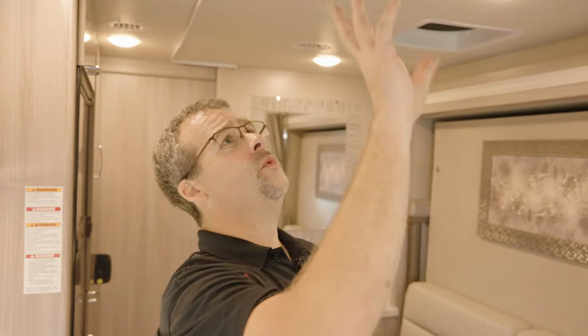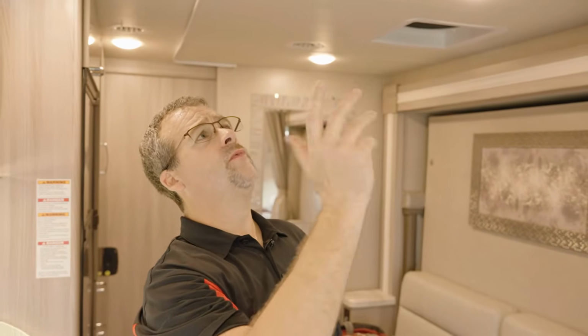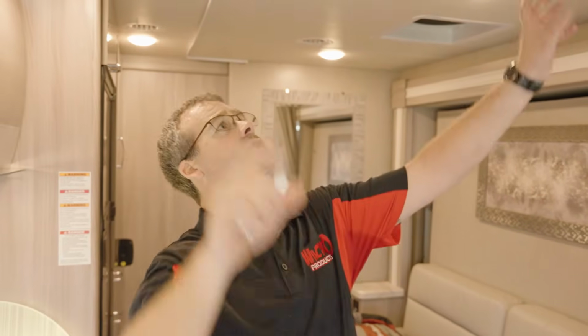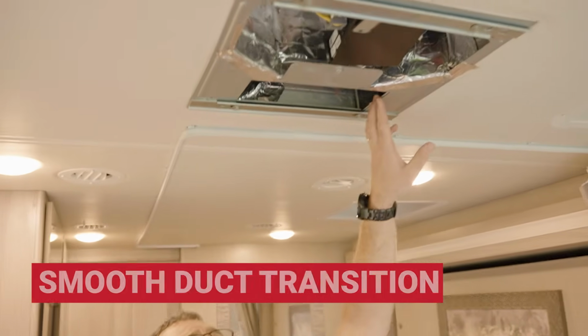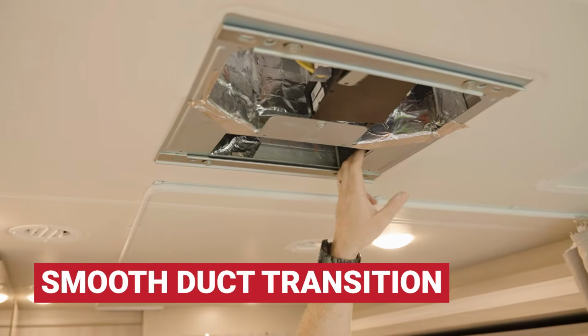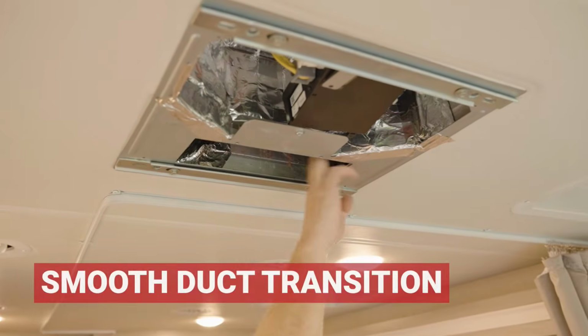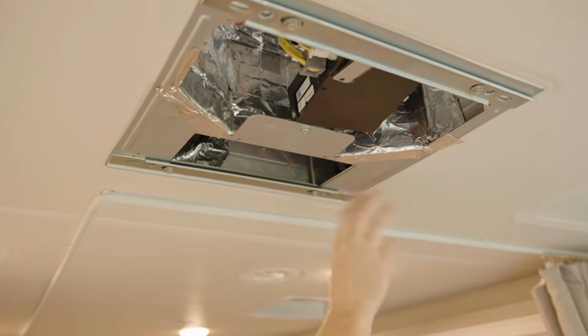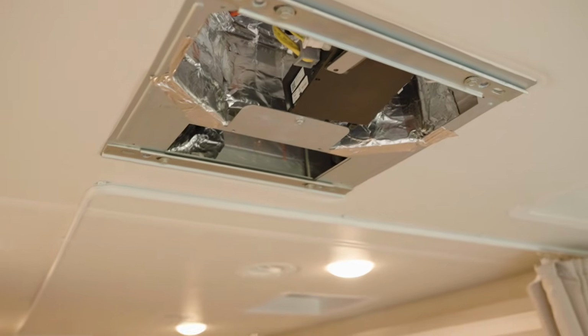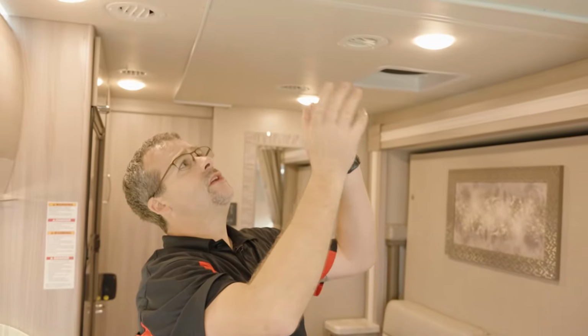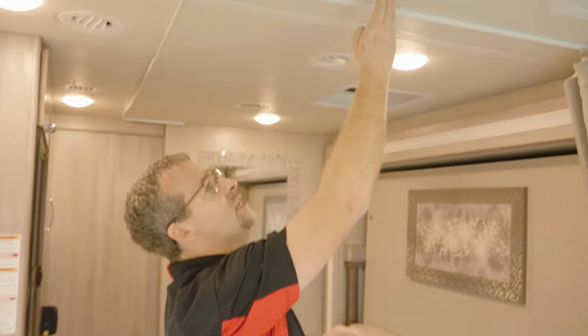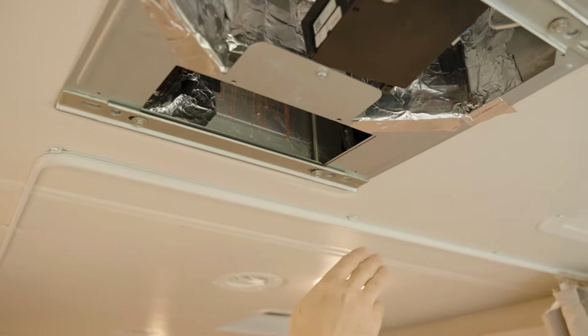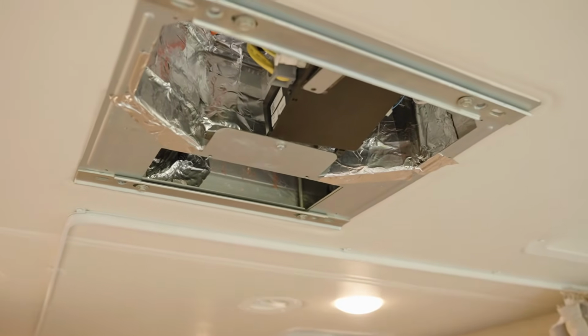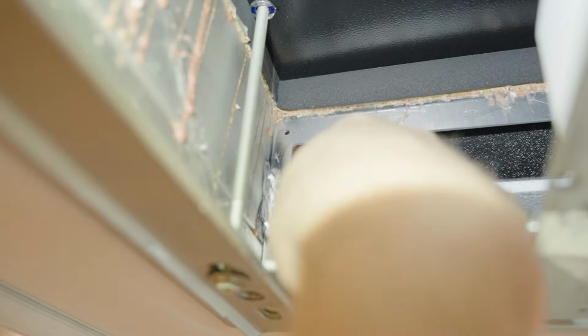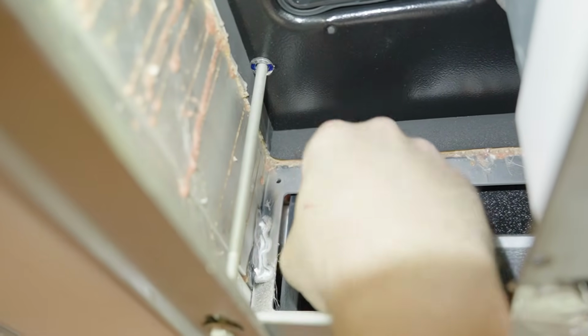So we got all the other repair work done up in the ceiling except for one item we need to look at, and that was where your ductwork ties into the supply side of the air conditioner. On the back side here, you'll look up in the holes left and right side—this particular unit is where the ductwork enters. We want to make sure that transition is smooth, wide open and clear, no holes leaking into the ceiling and missing the ductwork. In this example, we actually do have holes and gaps in the backside that we are going to go up there and seal up next.